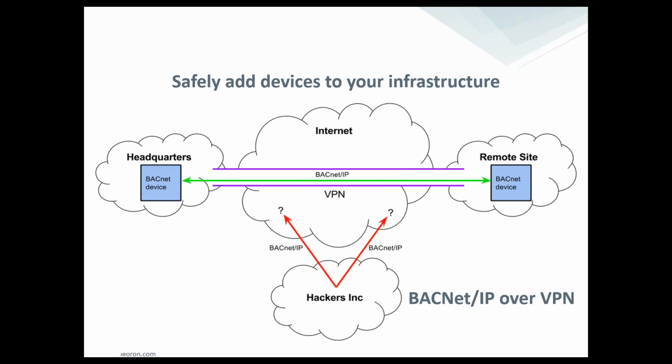But the other thing is that we can put all of our devices behind our firewalls, and if we need point-to-point communication so that we can access our HVAC system or our BACnet devices, we can do that over a VPN tunnel, which is encrypted, and the communication sits between the firewalls. That is a far better way to set up your network.